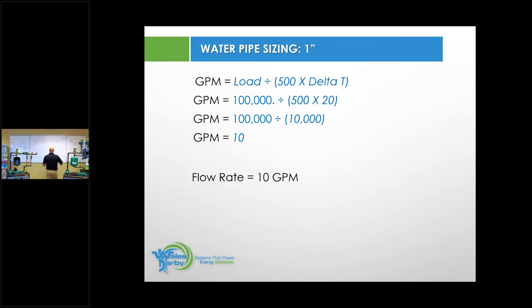So I'm going to go over to the board. I'm going to put 20 right here. 20 times 500, and that's going to give me 10,000. So what that's telling me is this gallon of water has the ability to absorb 10,000 BTU and deliver 10,000 BTU over the course of that hour, right? So this is the start of understanding what I'm using as a heat medium, which is water, what I'm using for my heat emitters, and how I'm going to take the energy that this boiler produces and deliver it to my system.